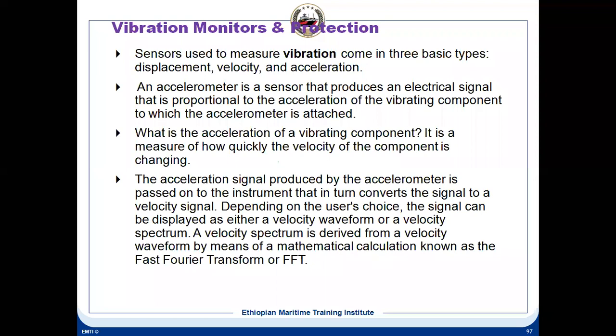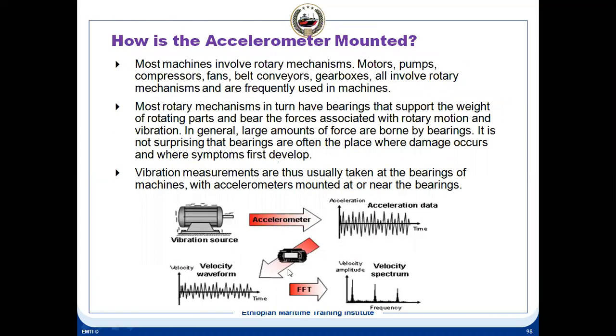The acceleration signal produced by the accelerometer is passed to an instrument that converts it into a velocity signal. Depending upon the user's choice, the signal can be displayed as a velocity waveform or a velocity spectrum. The velocity spectrum is derived from a velocity waveform by means of a mathematical calculation. This is the accelerometer sensor here, this is the vibration source, and this is the acceleration data. When you convert this data into a velocity spectrum, you get this. You see this amplitude; that means the velocity signal is very high, which means the vibration is very high. Most machines have rotary mechanisms.